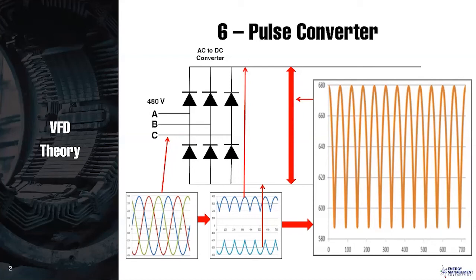So with 2 very simple measurements on the drive with a standard volt-ohm meter, you have tested that diode. You do the same thing between P and B and P and C, and then you do the same thing between A and N, B and N, C and N. You've got 12 simple tests there. And if you get continuity where you shouldn't, then you have a shorted diode. If you have no continuity where you should, you have an open diode. So this is a fairly quick test. Barry tells me this is one of the first things he does after he gets the drive open.